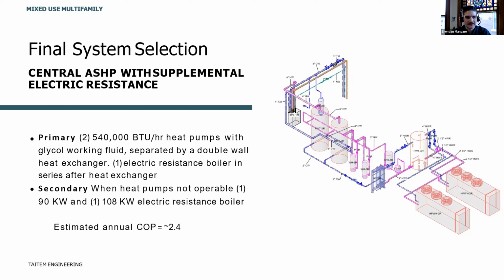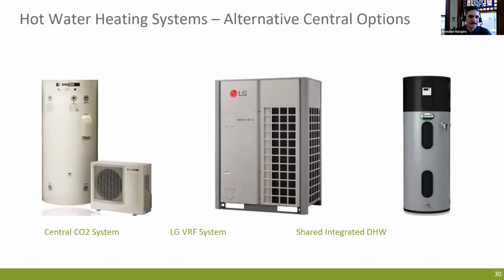So we're hoping that this really doesn't kick on very often, but if it gets below that -5°F, then we will need to rely only on electric resistance. And these boilers are a 90 kilowatt and then a 108 kilowatt. So a lot of energy going to those.